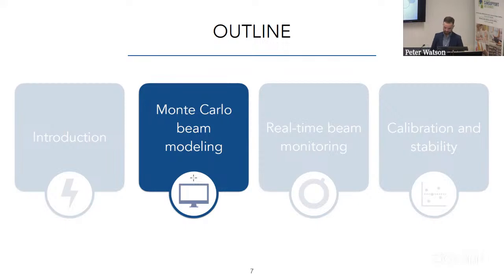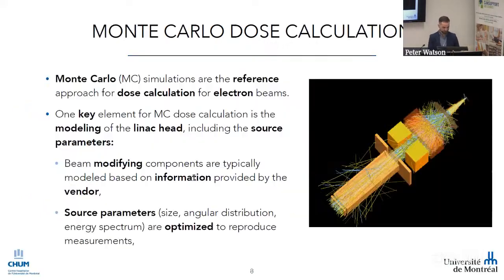these issues. So the first part of my talk will be on Monte Carlo beam modeling. So for electrons, we know that the reference approach for dose calculation is Monte Carlo. That's what we do clinically. So that's probably what we should do in an experimental setup like flash radiotherapy. And one key element for dose calculation in Monte Carlo is to have a good model of your beam. So typically we'll model the linac head and the beam modifying components like jaws and scattering filters using information provided by the vendor. And then the source parameters, the spot size, the distribution, and the energy spectrum will typically be optimized using measurements. We'll try to reproduce measurements by fine-tuning these parameters.